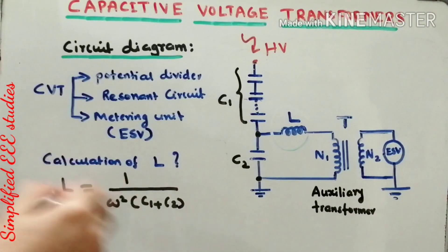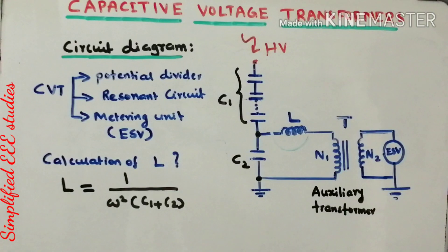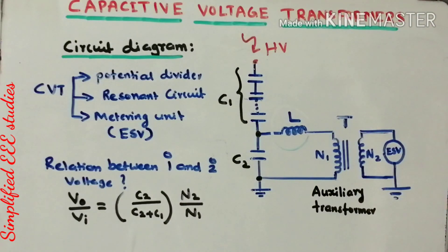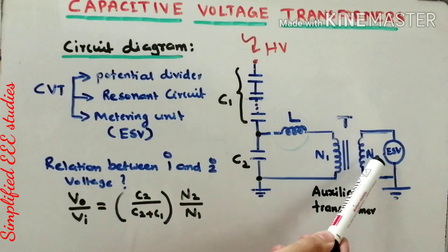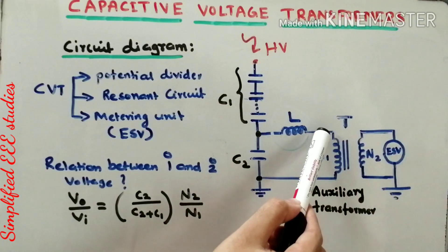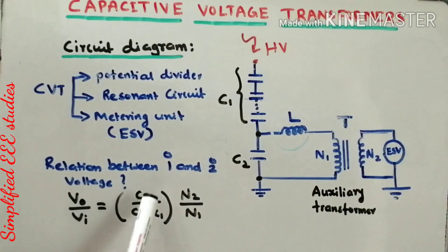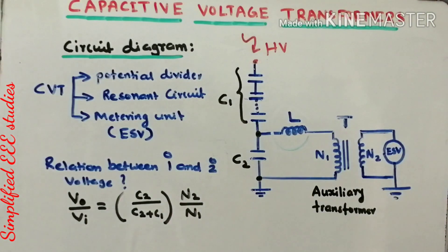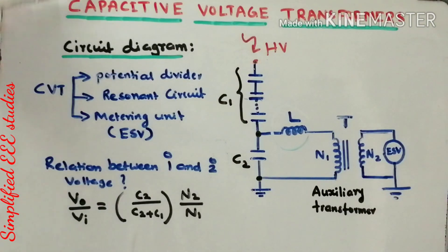There is also a relationship between the primary and secondary sides of the transformer: V0 / VIN = [C2 / (C2 + C1)] × (N2 / N1), where N2/N1 is the turns ratio. The value of C2 / (C2 + C1) will be less than 1. This relation between the primary and secondary sides of the auxiliary transformer is helpful for designing a CVT in a power system.